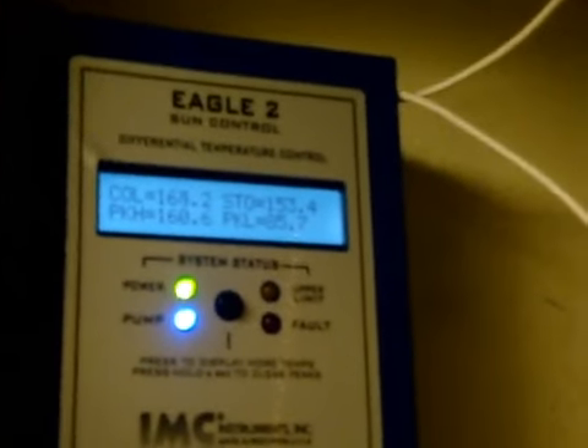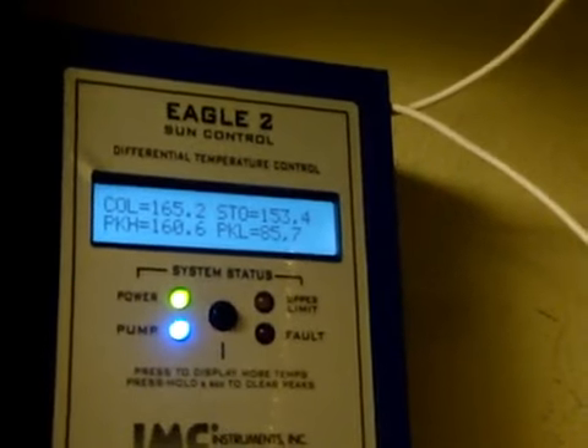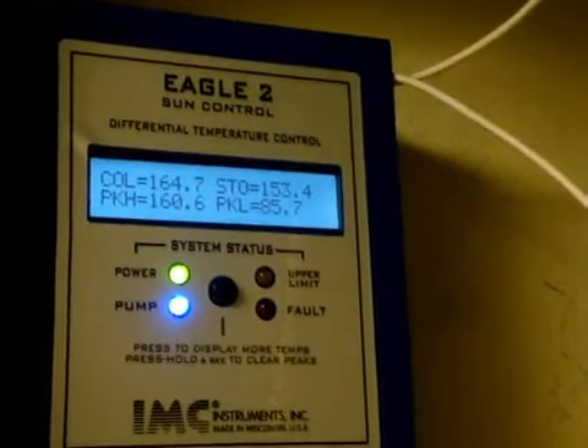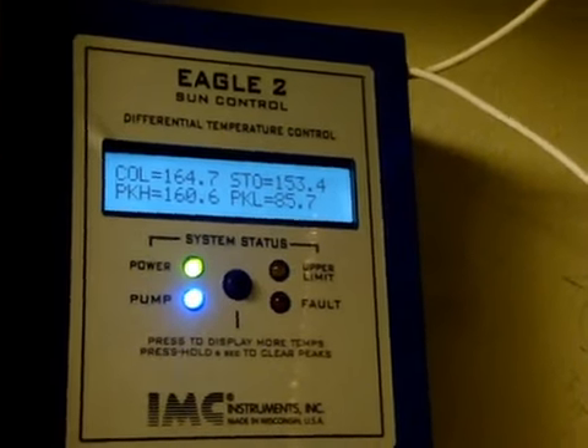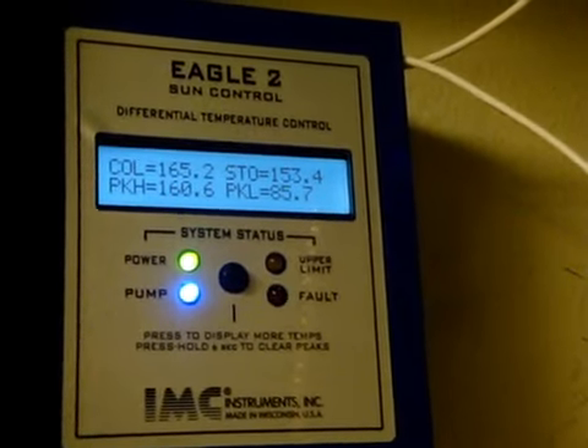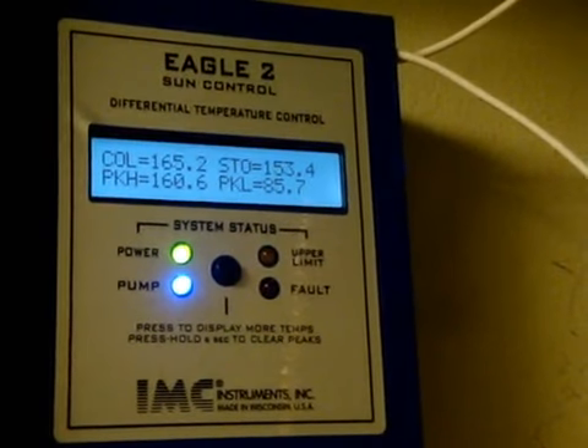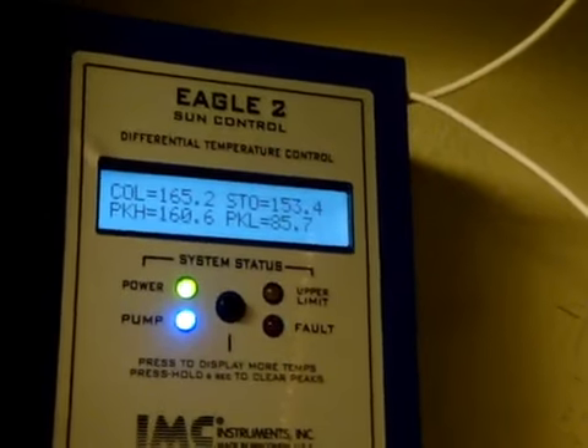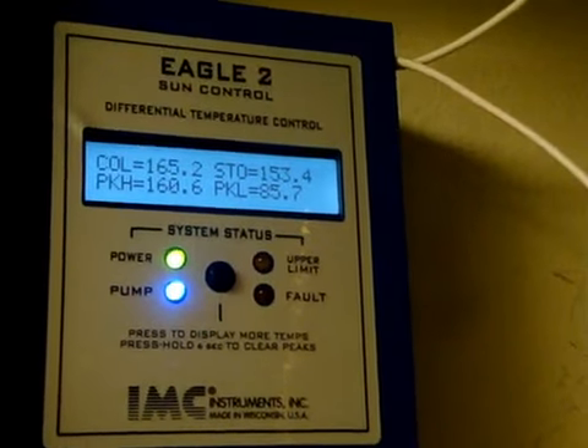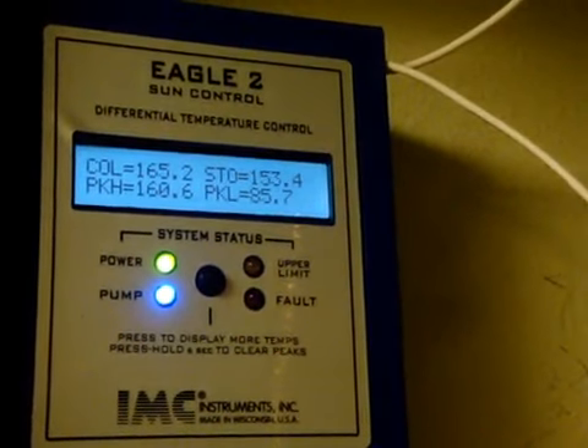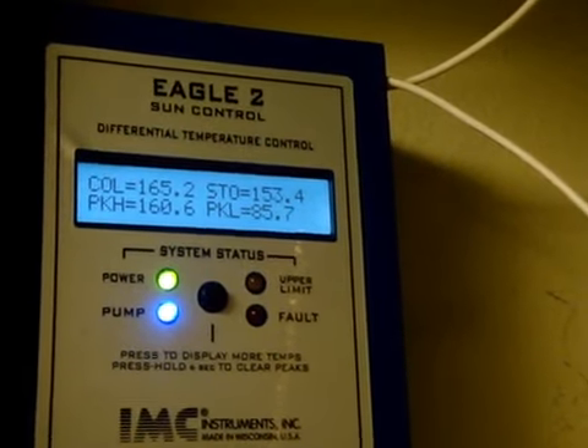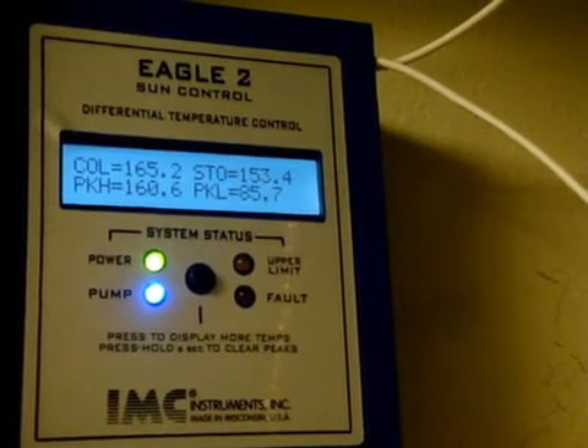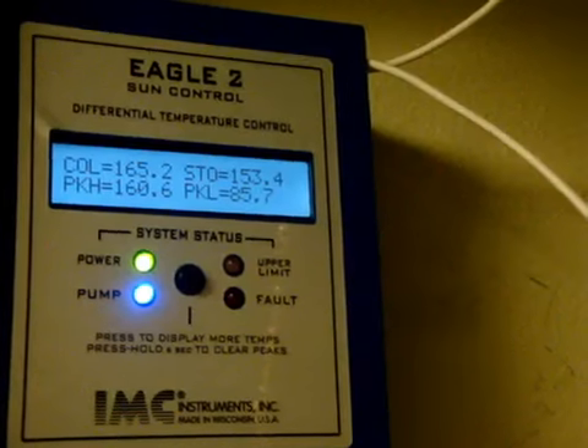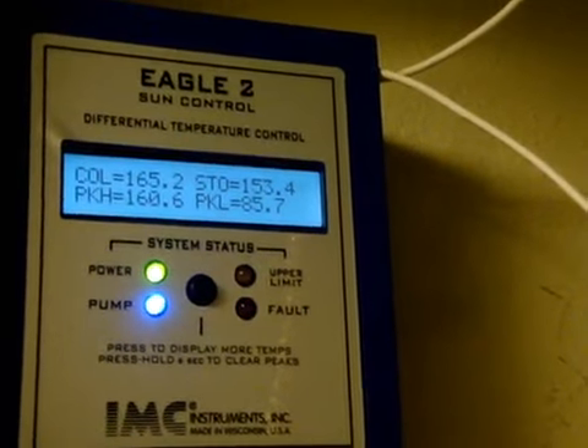Like I said, there's a heat exchanger up in the attic with a heat exchange fluid in it, and there's another pump up there that pumps the heat fluid through the collector on the roof and back into the heat exchanger. So there are two loops going. When the system shuts down, all the water on the roof comes back into the heat exchanger, so you have no freeze problem at all. There's no way it can freeze, which is nice. It works automatically. I have it set to 160, and when the storage tank gets to 160, it shuts down.